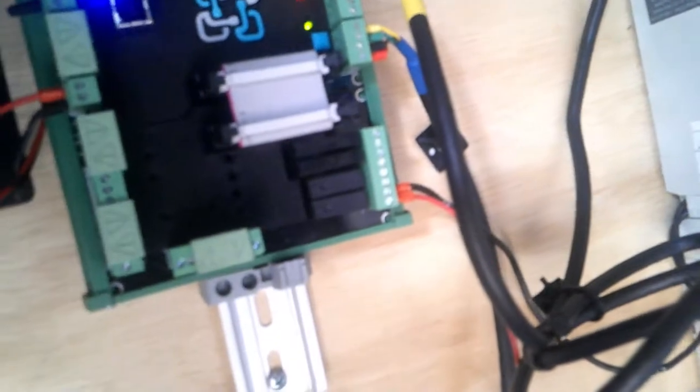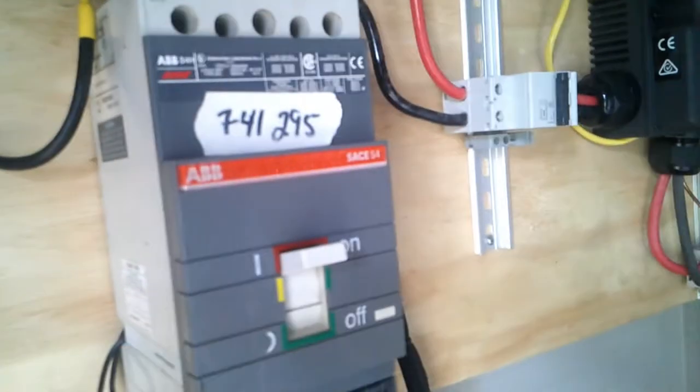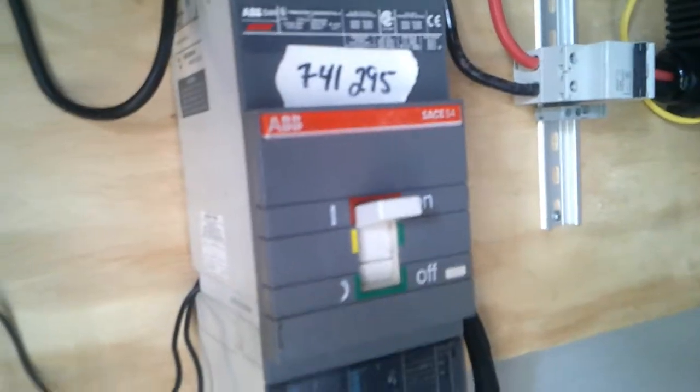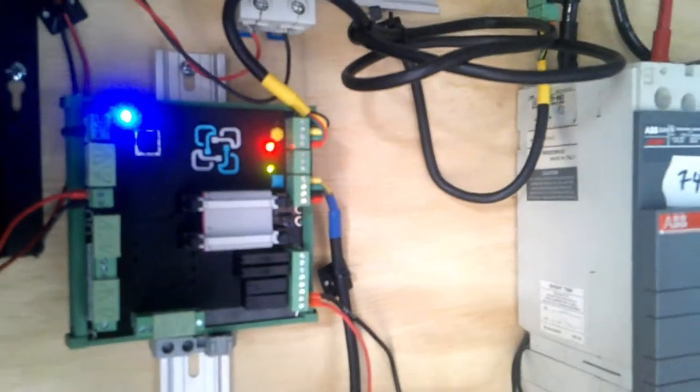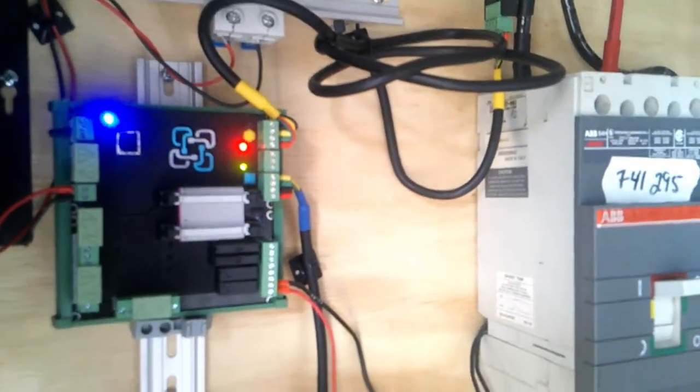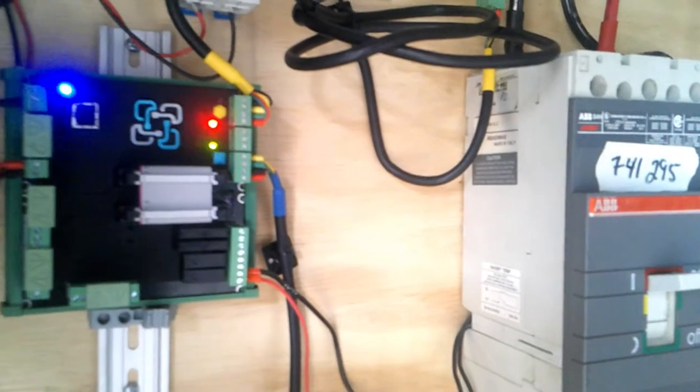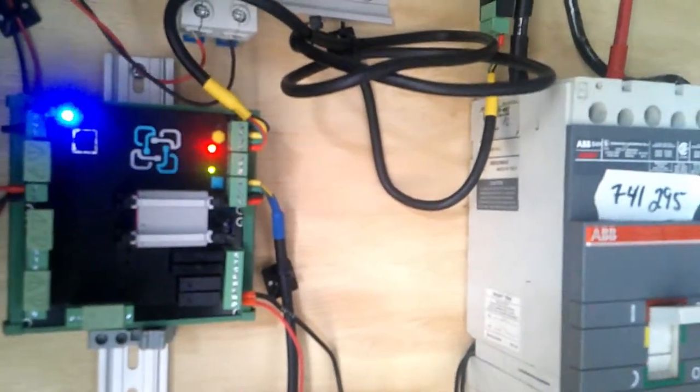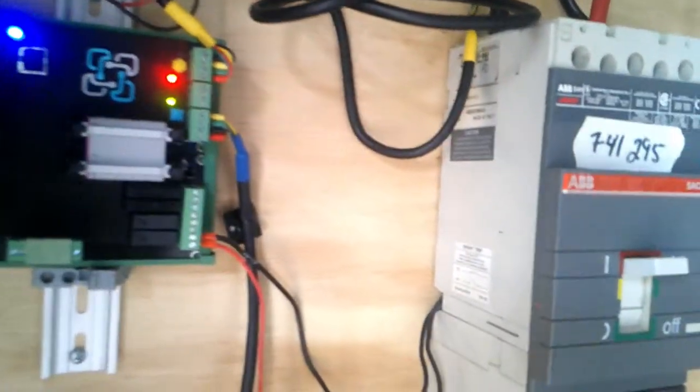So there, now the red 24 volts is switched by this relay on the BMS which I have set to a critical fault, which means when there's a critical fault, which basically means the battery voltage goes too high or too low, that's going to switch that relay on and put 24 volts to the ABB circuit breaker and switch it off. So that if there's a critical fault, the battery gets charged too high or too low, the BMS will put a critical fault out, switch the relay to closed, that's going to complete the circuit, 24 volts causes the circuit breaker to trip and it's going to shut everything down.